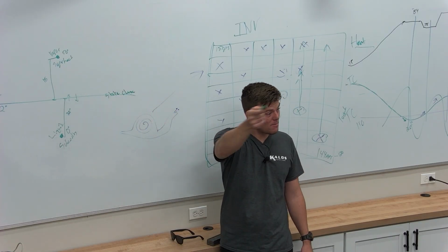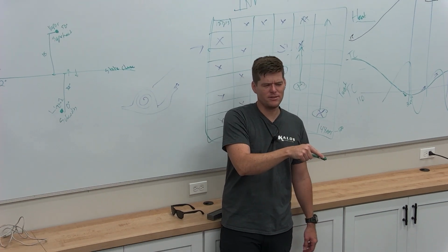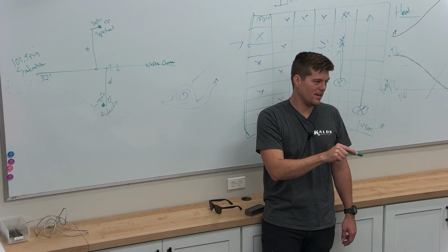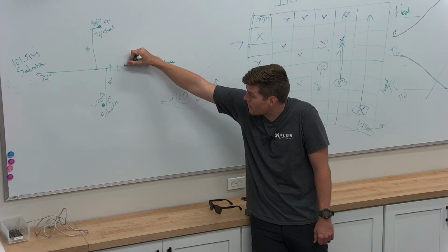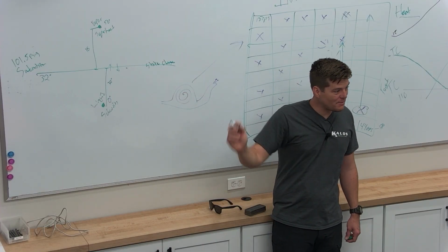And so then I follow it back. Where it was a vapor, it was supposed to become a liquid. Did it ever become a liquid? Well, no, it's a 1 degree subcooling across my indoor units in heating. Well, if it barely became a liquid right here, right? That's me. And then it's coming back to my outdoor unit.